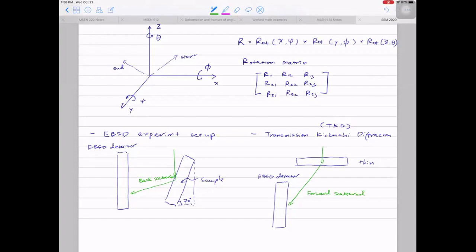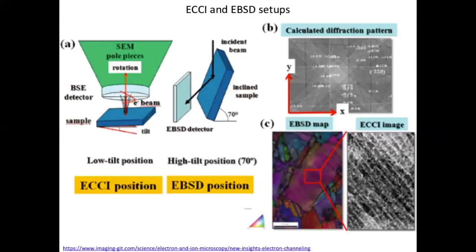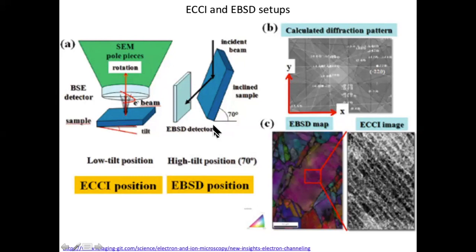This lecture covered two topics: ECCI (electron channeling contrast imaging) and EBSD (electron backscatter diffraction). For EBSD, the setup involves a 70-degree tilt and capturing backscattered electron diffraction on the detector. For ECCI, it's similar to regular SEM imaging — the sample lies flat with a very good surface, the stage is raised to bring the sample close to the detector.